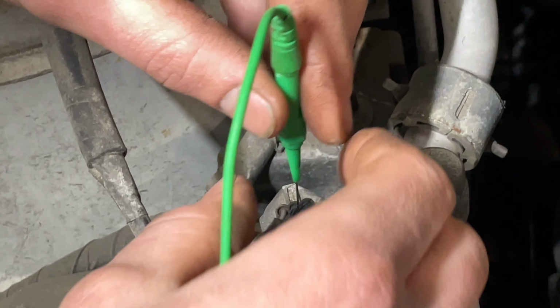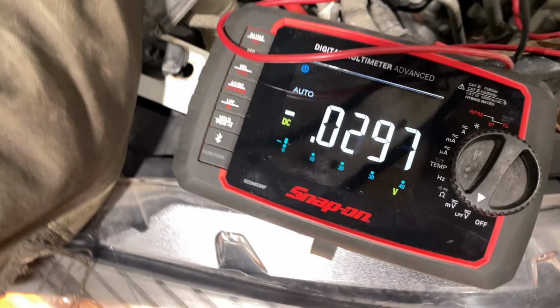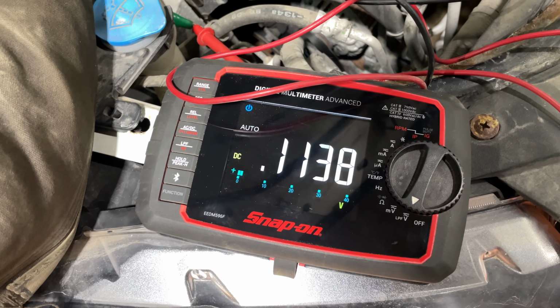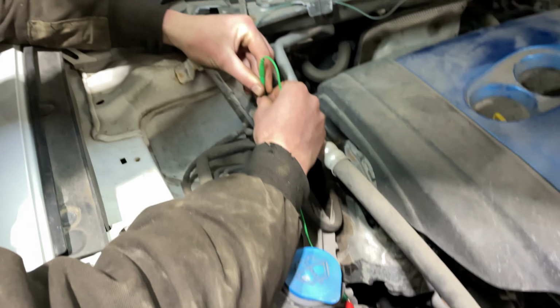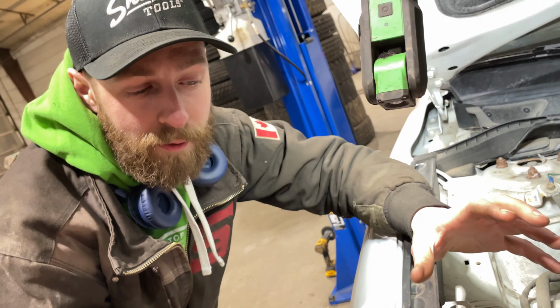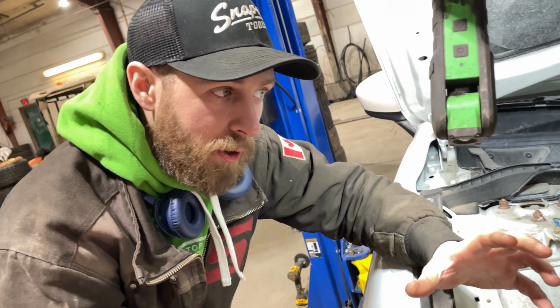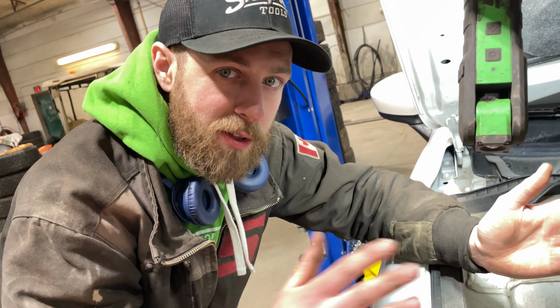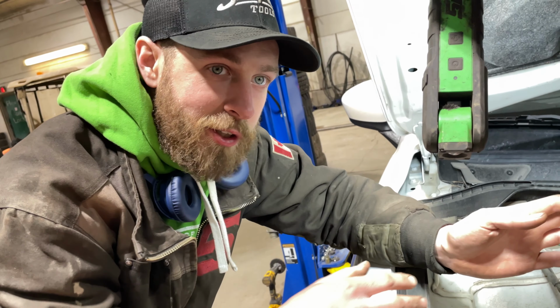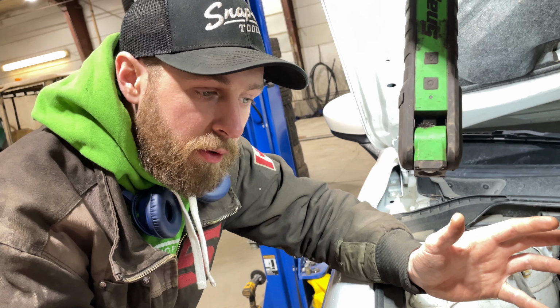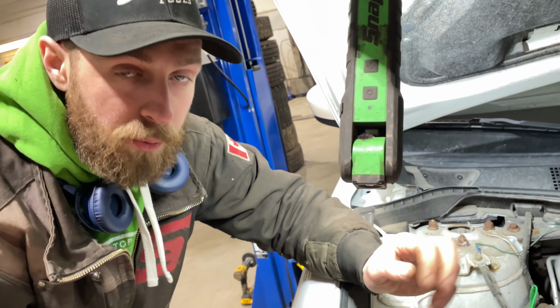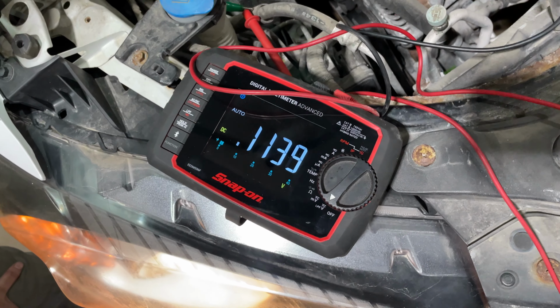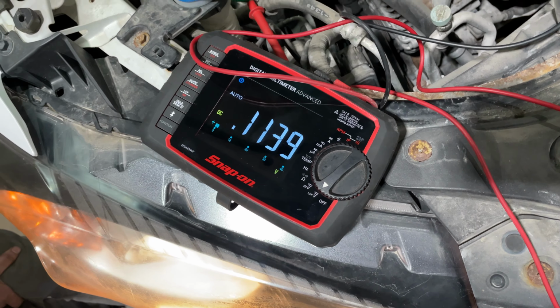And I'll just back probe this so you can see on the multimeter what reading we've got there. 0.11. Yeah. And then this gray wire, sneak down in there, that's our 5 volt reference. So I'm guessing, I don't know what signal we should see, like what determines high and low. Is close to 0 low pressure up to 5, or close to 5 high pressure? That's what I'm assuming. So in this case, I'm assuming we have low pressure. And this sensor is on the high pressure line, so I would expect it to be somewhat high pressure.